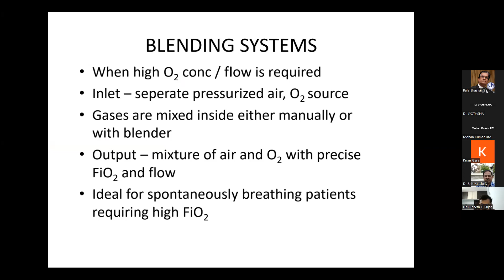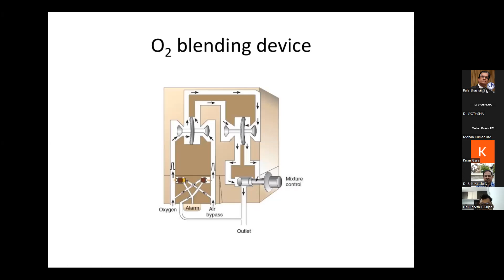Here we can see the blending system unit. There is an inlet for oxygen and air and an outlet for oxygen at the desired amount of flow. The oxygen and air are mixed either manually or with the help of blending systems. We also have alarms for oxygen failure or any drop in pressure.